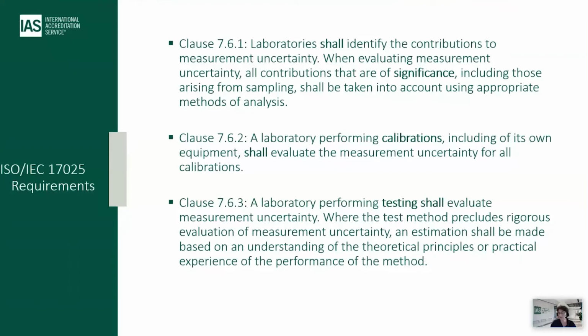In clause 7.6.3, a laboratory performing testing shall evaluate measurement uncertainty. Where the test method precludes rigorous evaluation of measurement uncertainty, estimates shall be made based on the understanding of the theoretical principles or practical experience of the performance of the method. Now, you see here in clause 7.6.3 that applies to testing laboratories.